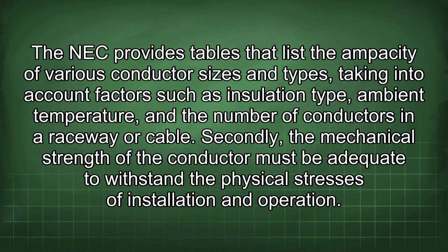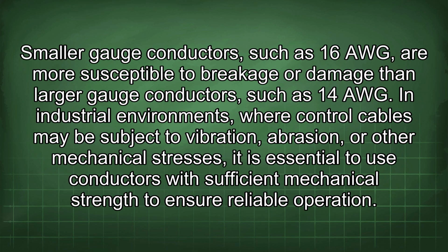Secondly, the mechanical strength of the conductor must be adequate to withstand the physical stresses of installation and operation. Smaller gauge conductors, such as 16 AWG, are more susceptible to breakage or damage than larger gauge conductors, such as 14 AWG. In industrial environments where control cables may be subject to vibration, abrasion, or other mechanical stresses, it is essential to use conductors with sufficient mechanical strength to ensure reliable operation.